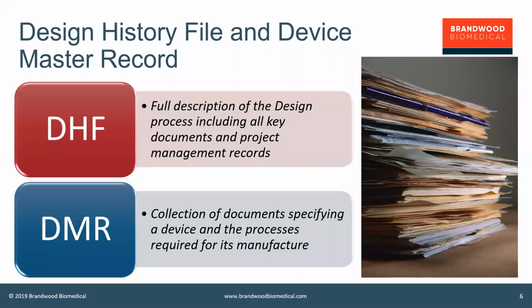So that's the nitty-gritty of what a technical file is. Now let's talk about how that relates to a DHF and a DMR. As we described earlier, a DHF is the design history file, and that's the full description of the design, including any key documents and many project management records. So this is really how you developed and designed your device.